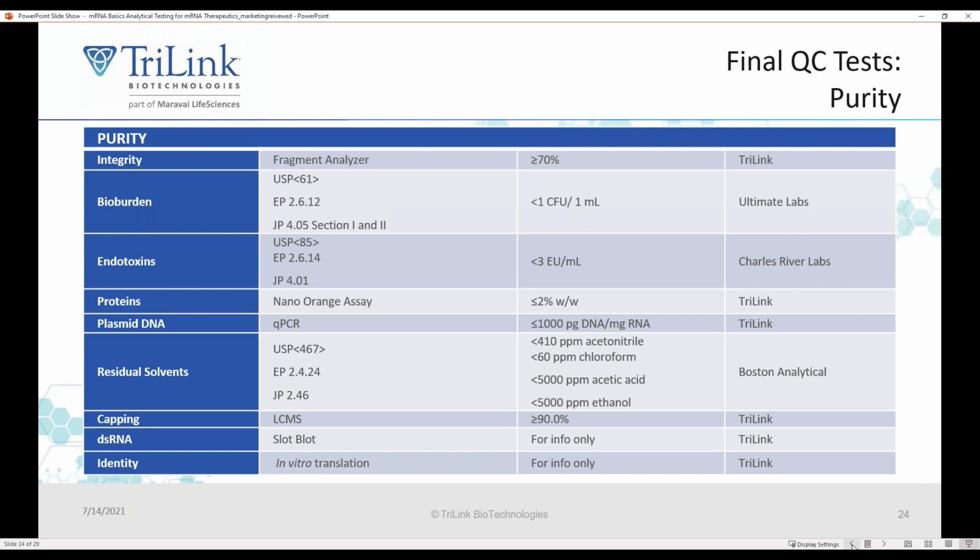In the case, though, that you're testing for a specification of, say, less than 1 CFU per 10 milliliters, now you'll need to test 10 milliliters for aerobic and 10 milliliters for fungus. In addition to that, you also have to perform suitability testing, which contains about 7 times the amount needed for regular testing. And then you also have to consider what the concentration of your product is.